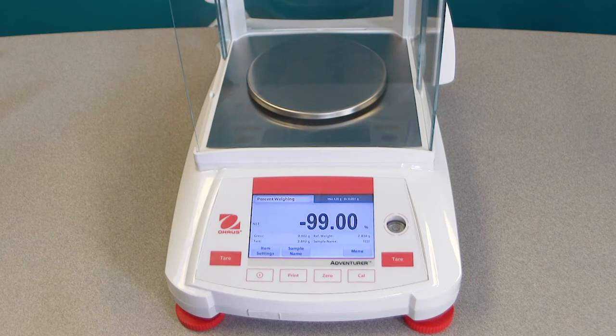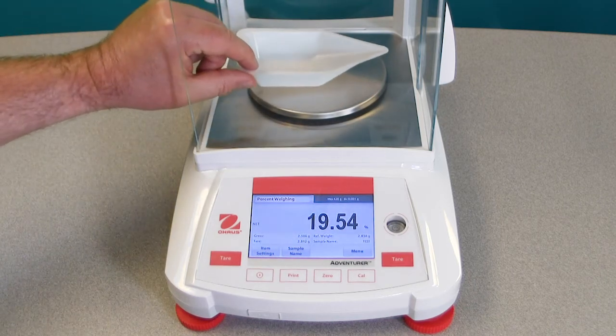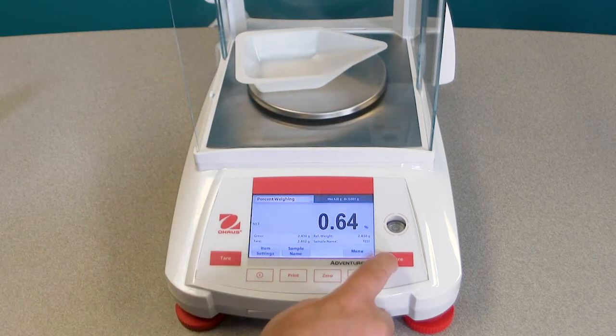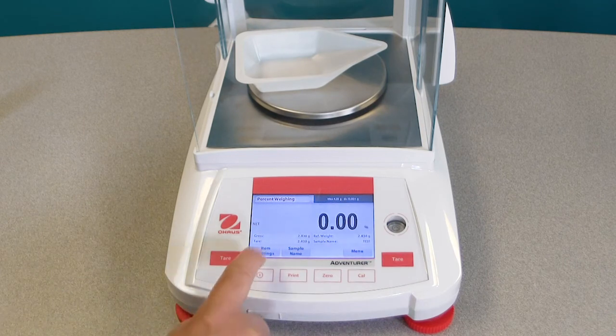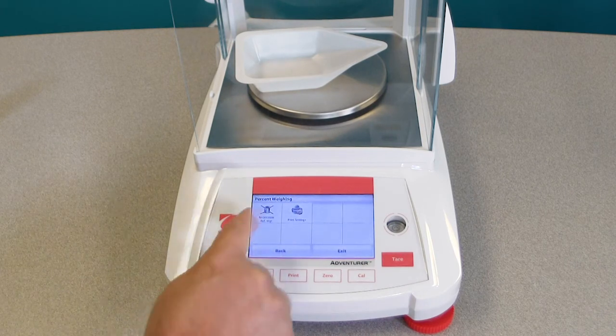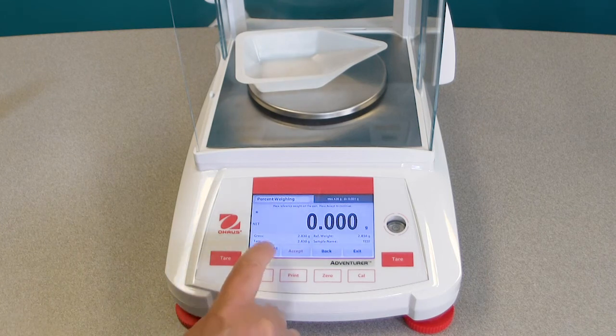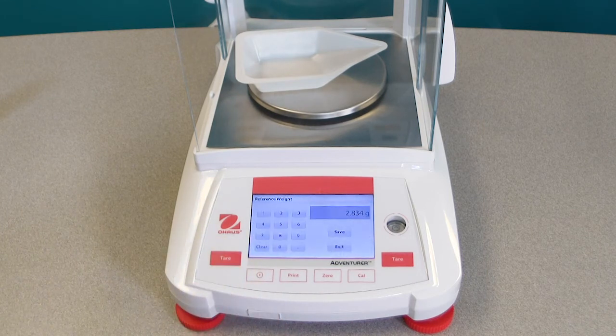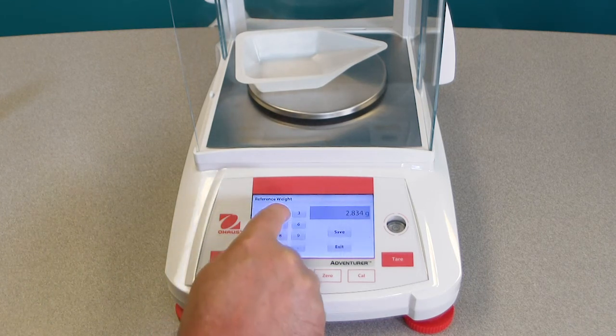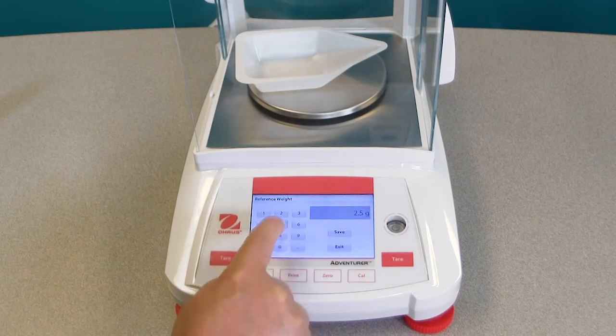Alternatively, you can forego placing an object on the pan, or place an empty weighing container on the pan to Tare, and press the Item Settings button, then Recalculate Reference Weight, then press Reference Weight in the lower left corner. From there, you can manually type in the reference weight from the keypad.